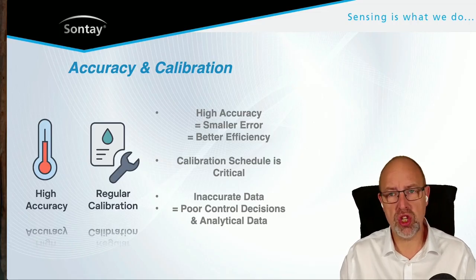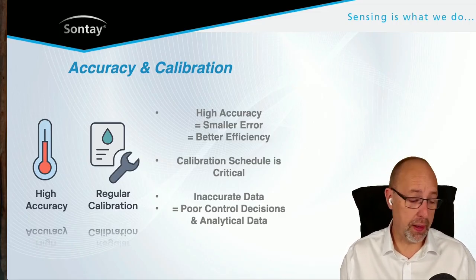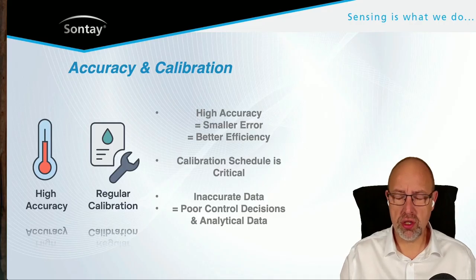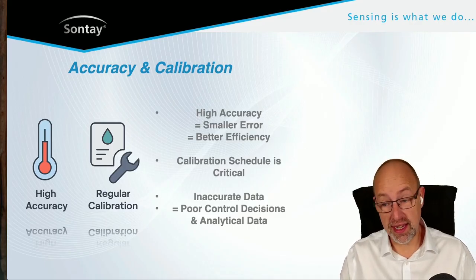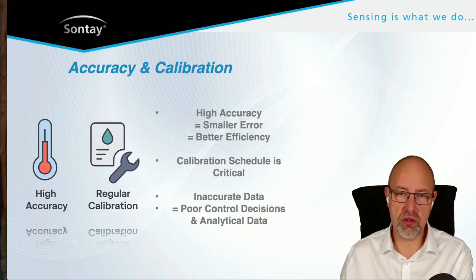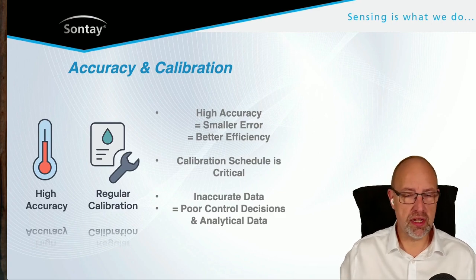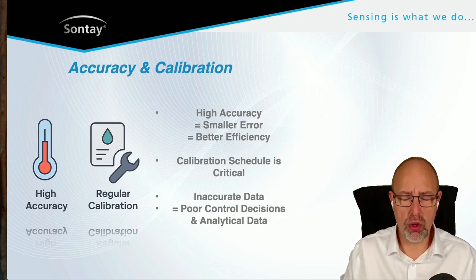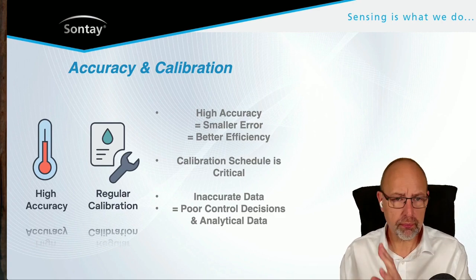We have to check and check again. Everything has to be calibrated properly. UKAS, UK Accreditation Service, are often involved. The sensors need to go off to a UCAS accreditation laboratory, come in, and then we test and we retest so that everything can be controlled very, very accurately.